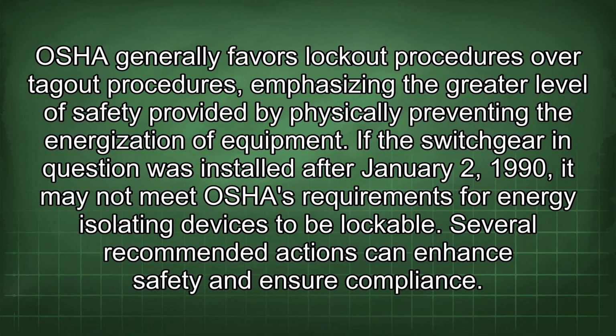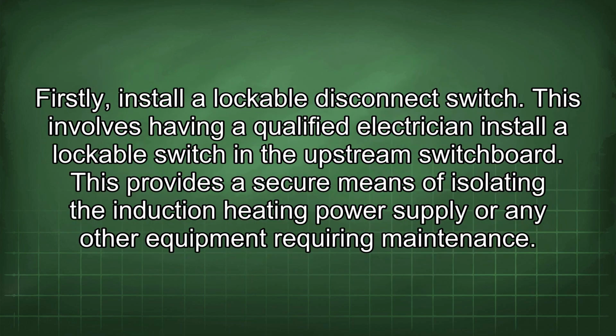Several recommended actions can enhance safety and ensure compliance. Firstly, install a lockable disconnect switch. This involves having a qualified electrician install a lockable switch in the upstream switchboard. This provides a secure means of isolating the induction heating power supply or any other equipment requiring maintenance.